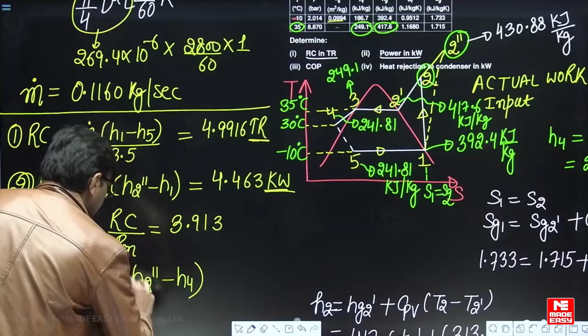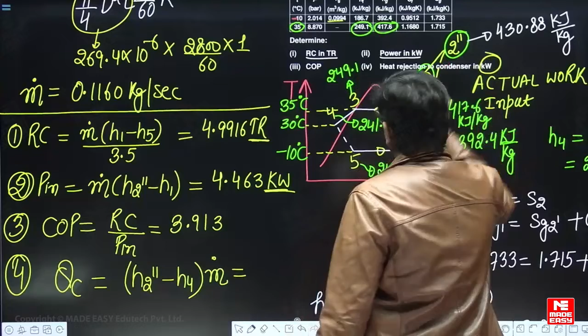And the heat rejection across condenser: the condenser entry is 2 double dash and exit is 4. So H2 double dash minus H4 into mass flow rate, because we have to find out the heat rejection across condenser in kilowatt.